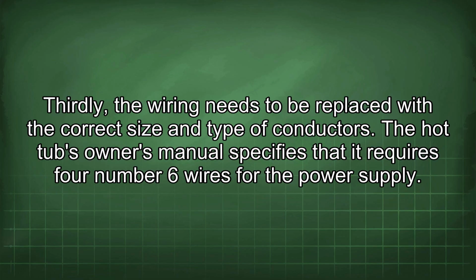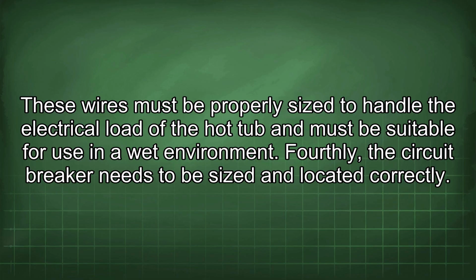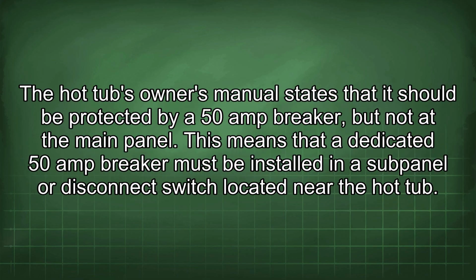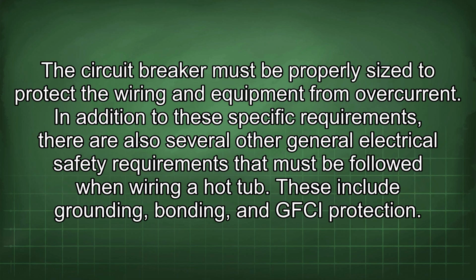Thirdly, the wiring needs to be replaced with the correct size and type of conductors. The hot tub's owner's manual specifies that it requires 4 number 6 wires for the power supply. These wires must be properly sized to handle the electrical load of the hot tub and must be suitable for use in a wet environment. Fourthly, the circuit breaker needs to be sized and located correctly. The hot tub's owner's manual states that it should be protected by a 50 amp breaker, but not at the main panel. This means that a dedicated 50 amp breaker must be installed in a sub-panel or disconnect switch located near the hot tub. The circuit breaker must be properly sized to protect the wiring and equipment from overcurrent.